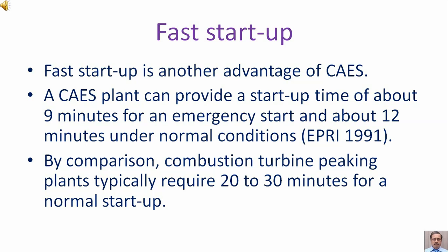Fast startup. Fast startup is another advantage of CAES. A CAES plant can provide a startup time of about 9 minutes for an emergency start and about 12 minutes under normal conditions. By comparison, combustion turbine peaking plants typically require 20 to 30 minutes for a normal startup.